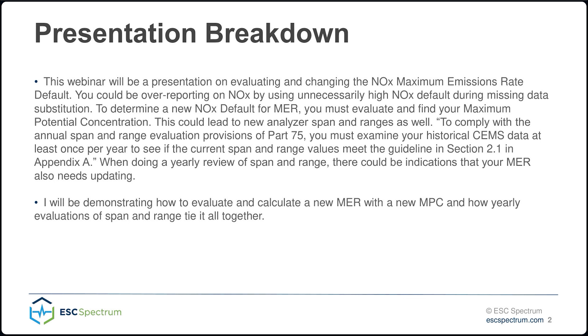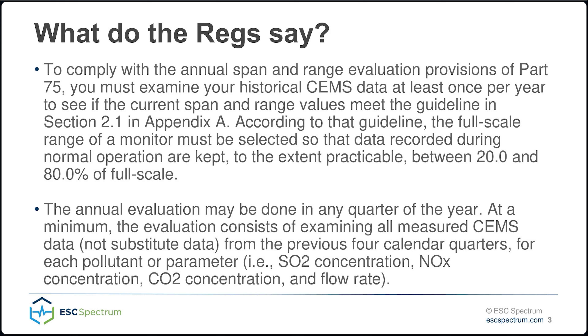Part of having a new analyzer span and range and how that ties into this is you're supposed to be evaluating your span and range every year as part of Part 75. You must examine your historical CEMS data at least once per year to see if the current span and range values meet the guidelines in Section 2.1 in Appendix A. This is a really good indicator if your MER needs updating. If you see that you're not complying with your current span and range, that's when you investigate, look for a new MPC, and then you're probably going to have a new MER because MPC is directly used in the equation for MER. Every year you should be doing a span and range evaluation.